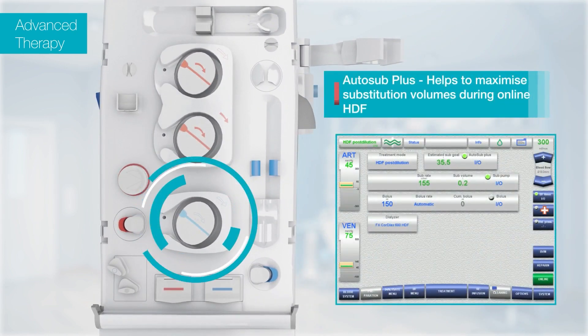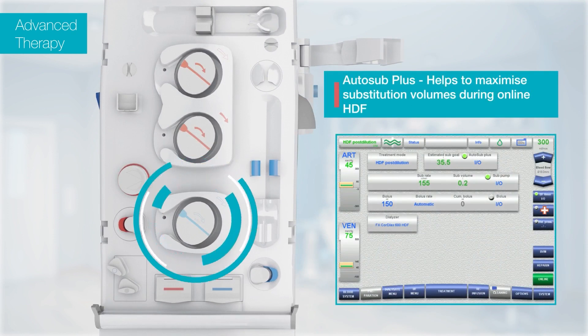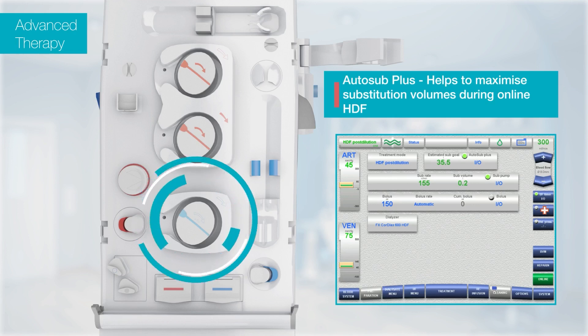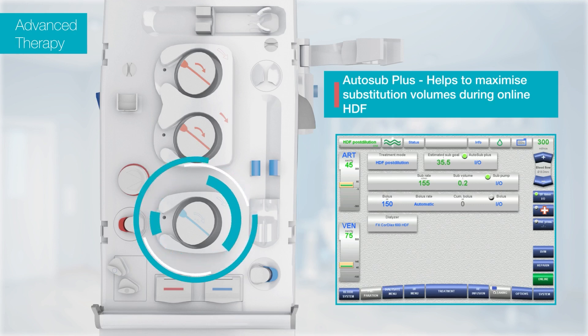The auto-sub-plus maximizes substitution volumes during online hemodiafiltration for high convective removal of middle molecules while avoiding haemoconcentration and filter clotting. This is achieved by continuous signal analysis of pressure pulses generated by the blood pump.